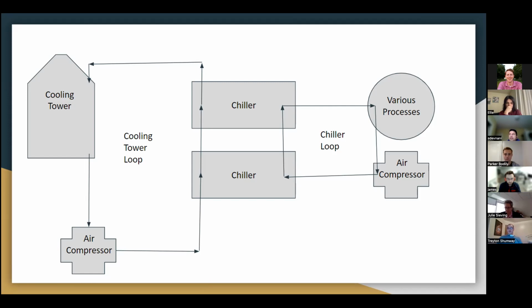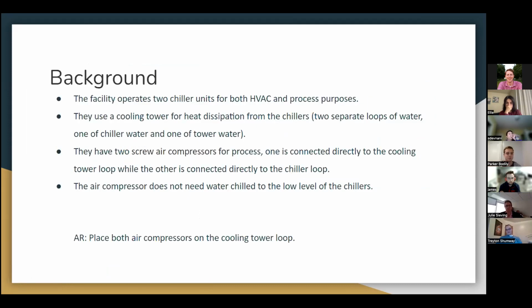The second set is just the chillers loop. So the chillers export their heat to the cooling tower loop, and then they cool various processes they use in the facility. I think there's other things that they use, but we're more worried about the air compressor. So it does one of the air compressors, and that's that chiller loop. So our recommendation is we're going to put that second air compressor onto the cooling tower cycle. So the chillers won't be cooling the air compressor, it'll be all the cooling towers, is what our recommendation would be.